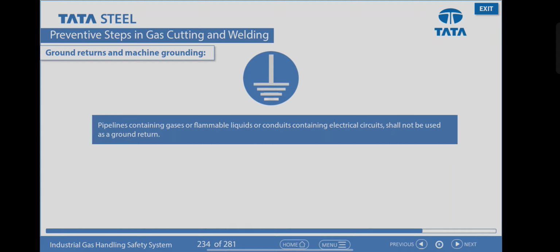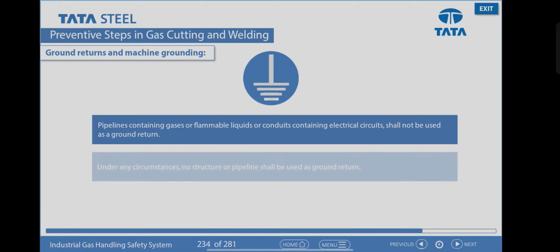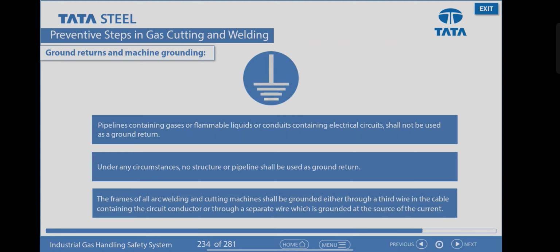Pipelines containing gases or flammable liquids or conduits containing electrical circuits shall not be used as a ground return. Under any circumstances, no structure or pipeline shall be used as ground return. The frames of all arc welding and cutting machines shall be grounded either through a third wire in the cable containing the circuit conductor or through a separate wire which is grounded at the source of the current.